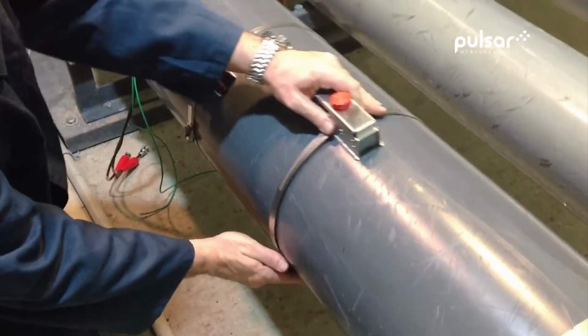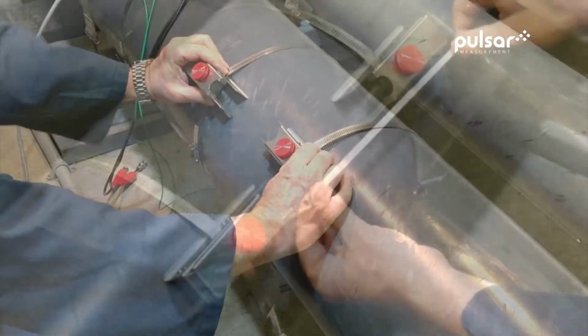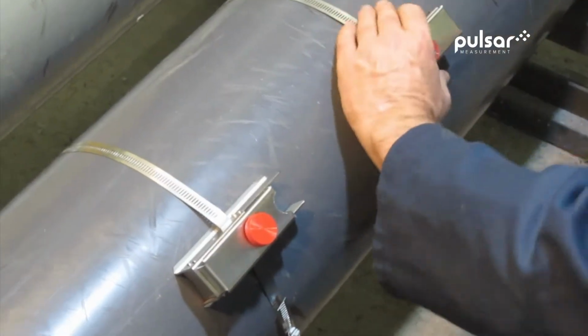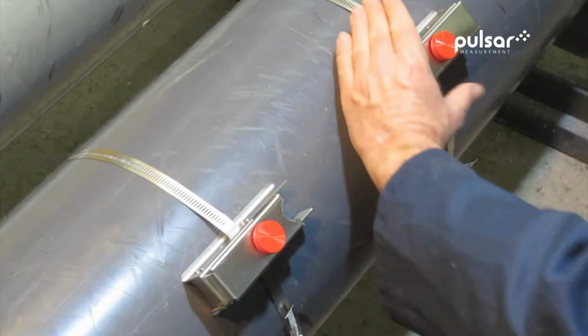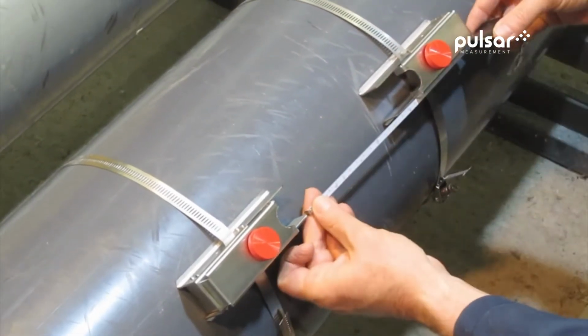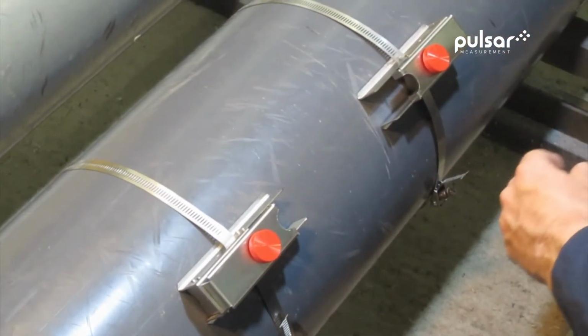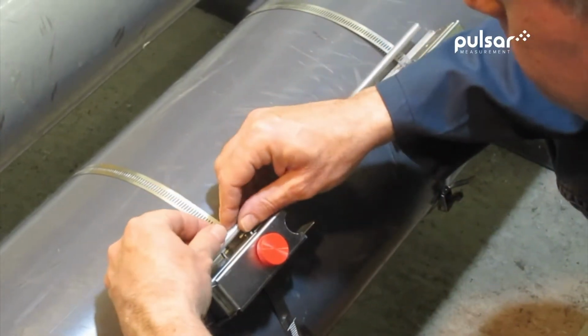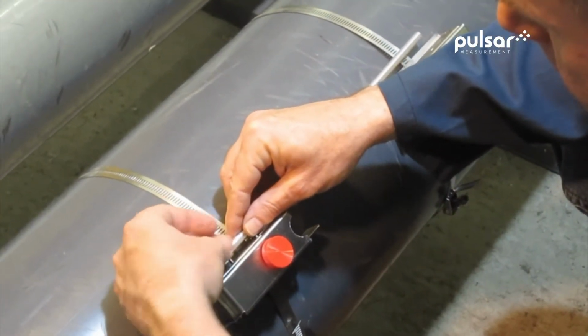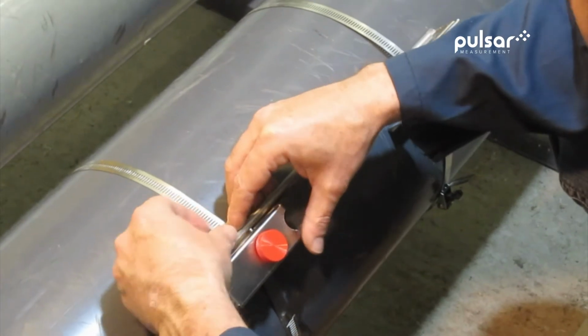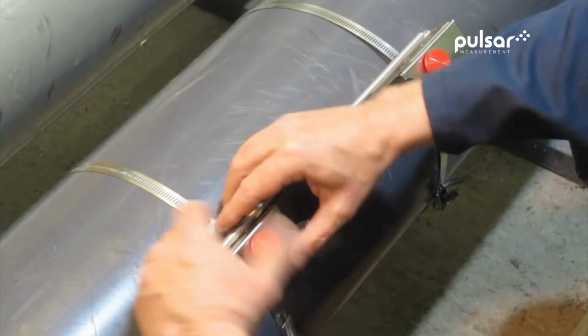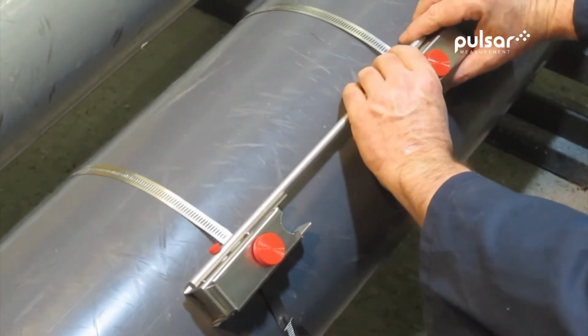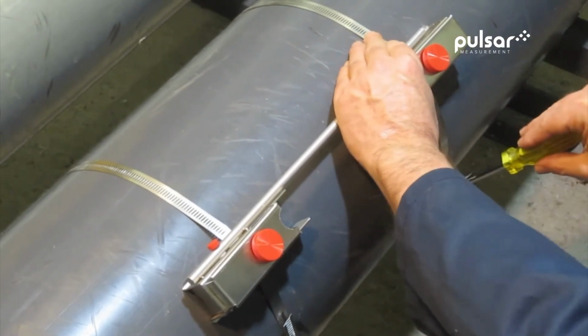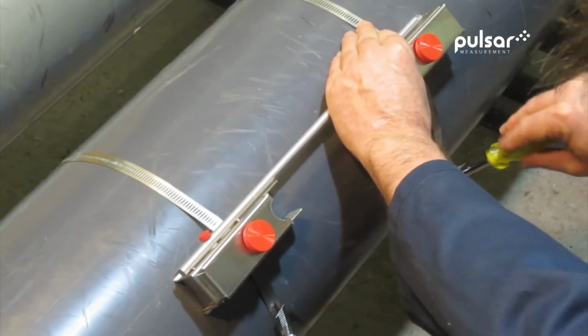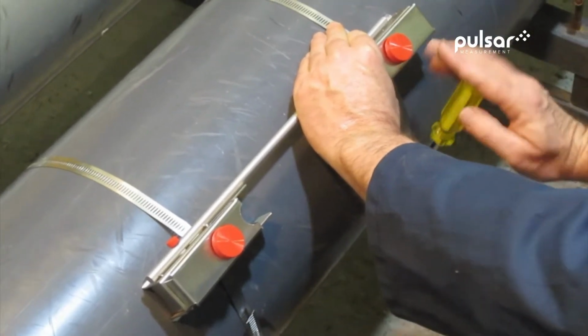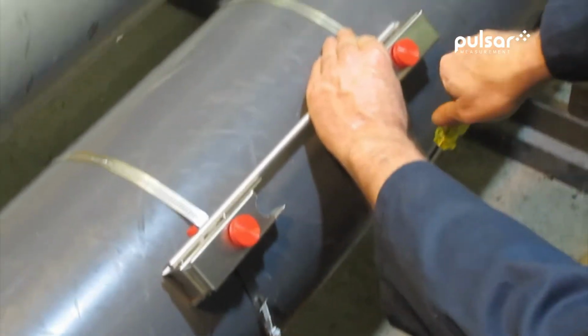The TTFM flowmeter calculates the transducer separation distance for us, so we position the mounting brackets and check with a tape measure or ruler. An alignment bar is included to help position the brackets properly on the pipe. Once the mounting brackets are tightened in place, we're ready to mount the ultrasonic transducers.